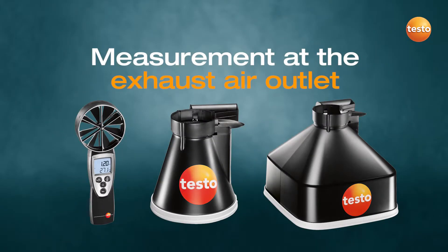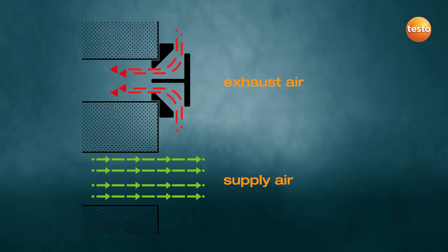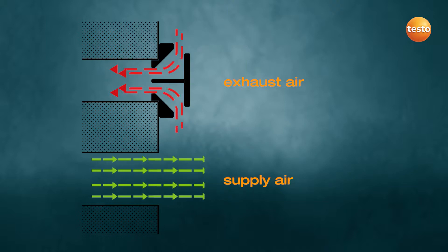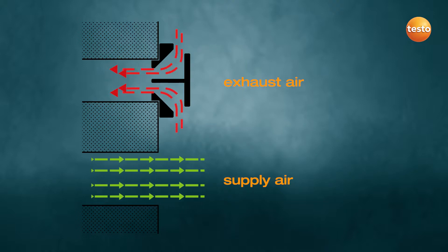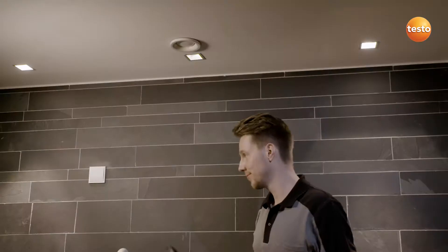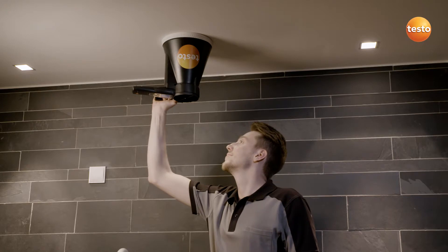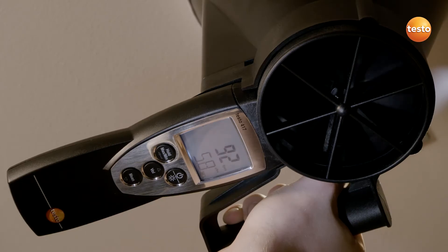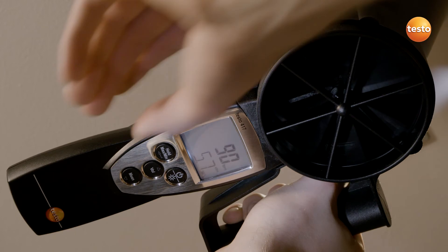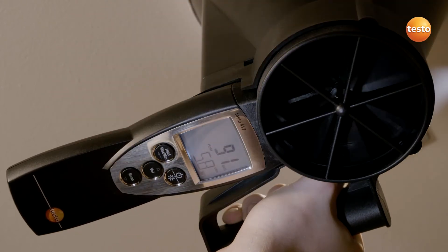This is how you measure properly at the exhaust air outlet. A funnel is required to measure the exhaust air. The reason: there is no directed flow profile available for exhaust air, as the air is sucked in funnel-like from the room. This means there is no definable area in the room via which the volume flow can be determined. This challenge is easily solved with the Testo 417 funnel, because it creates defined flow conditions at some distance from the plate outlet in a fixed cross section.